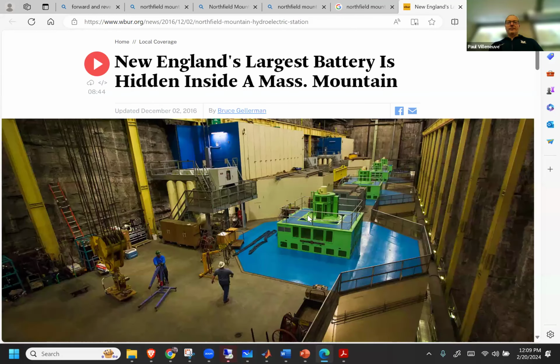These units here—this is the generator part, I mean the field part, called the pilot exciter, but right below it is the motor generator. So sometimes it runs as a generator, sometimes as a motor. That's why it's dual rated: 307 MVA or 291,000 horsepower, and that's output.